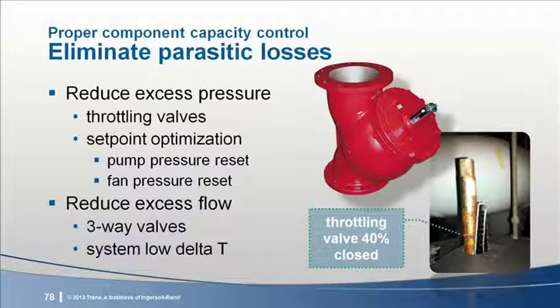Allowing an airside system to operate at a low chilled water delta T is a form of unmanaged parasitic loss. Increased flow packs a twofold penalty to energy consumption: the increase caused by greater mass flow, along with a greater system pressure requirement as a result of the pump energy rising to the cube of the parasitic flow increase.